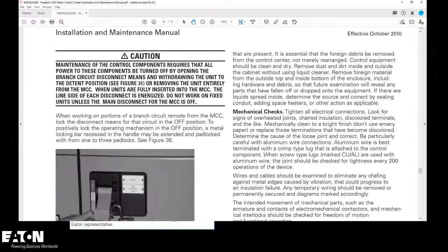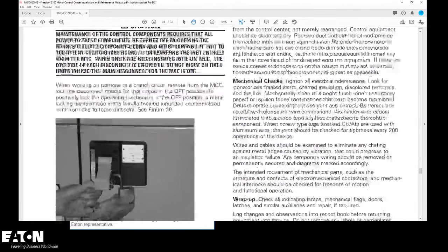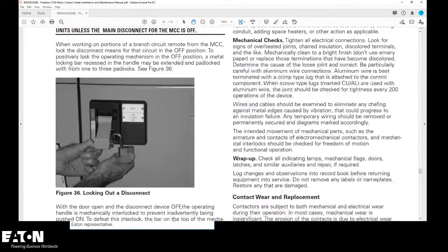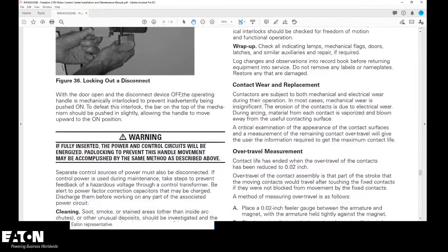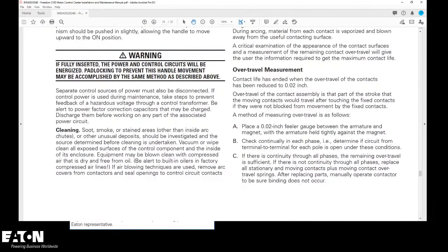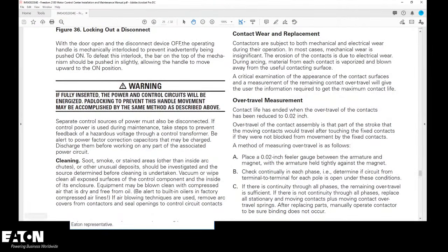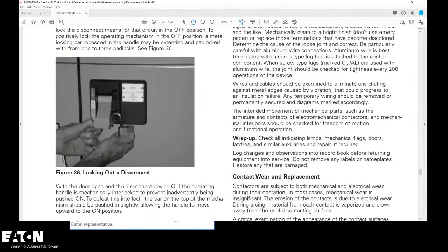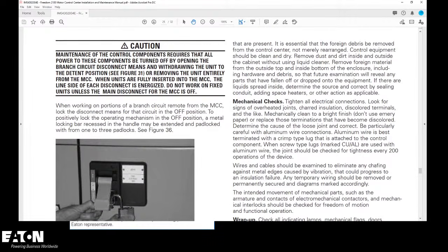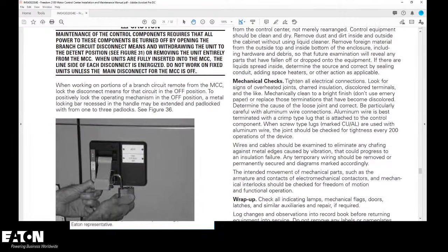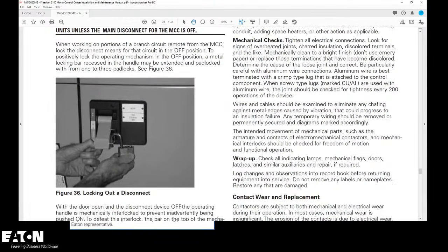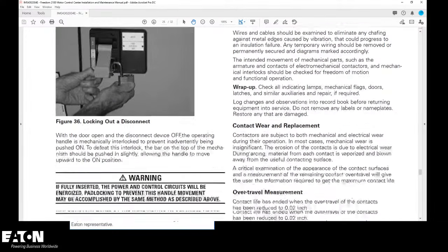And so we've got mechanical checks. We've got electrical tests that we can do. Cleaning: look for soot, smoke, stained areas, blown clean, and I would say de-energize it before you start getting in there with an air compressor, for goodness sakes. Remove arc covers from contactors. Okay, so we give you some good, half-decent outlines, and there are other standards, I'm sure, out there for motor control center maintenance, etc.